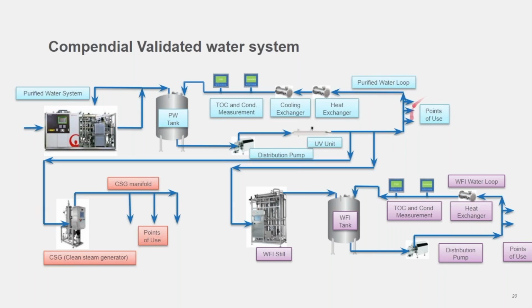And what we're trying to achieve there is the treated water quality spec. So if we take, for example, USP, United States Pharmacopeia, for purified water, we're looking at less than 1.3 microsiemens conductivity at 25 degrees, and less than 500 ppb TOC. And microbially, we're looking at less than 100 CFU per mil. So the idea is that we need to be within that spec to manage the risk for the product. If you have water that's out of spec, you have to throw the product away.